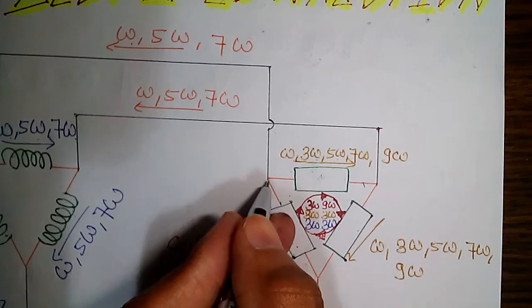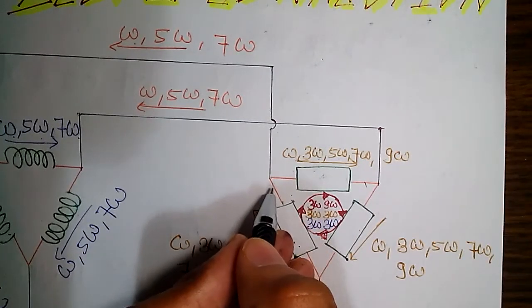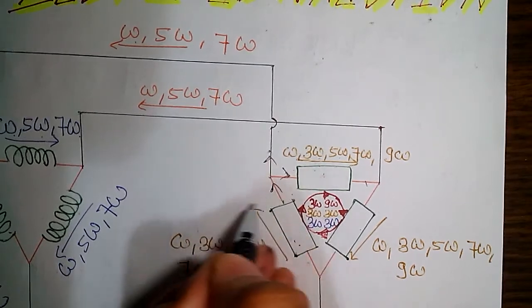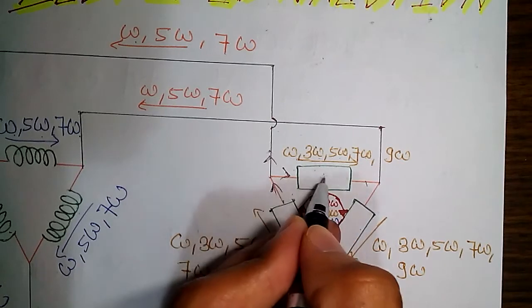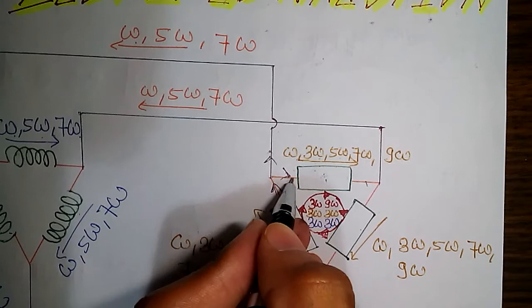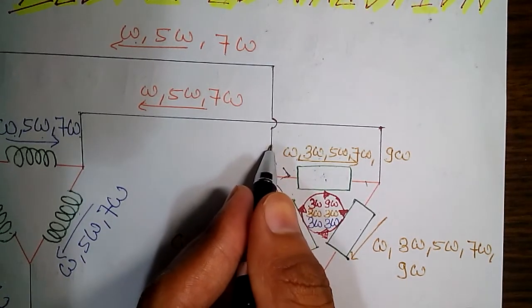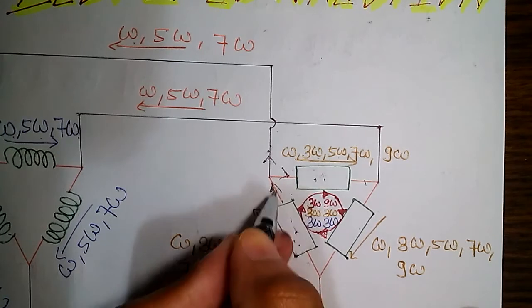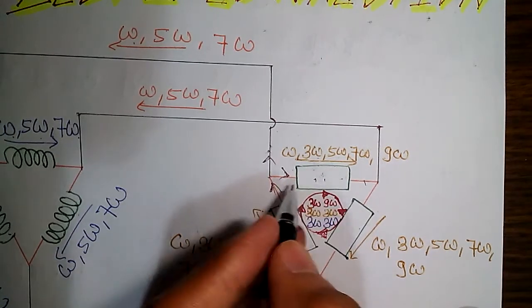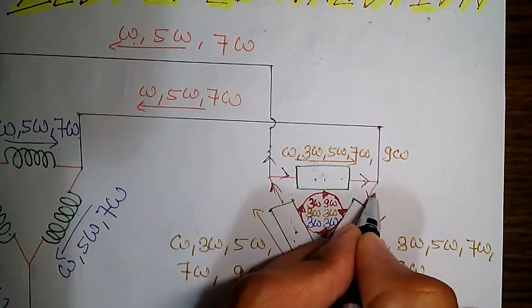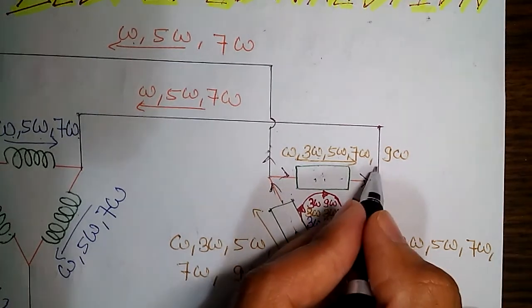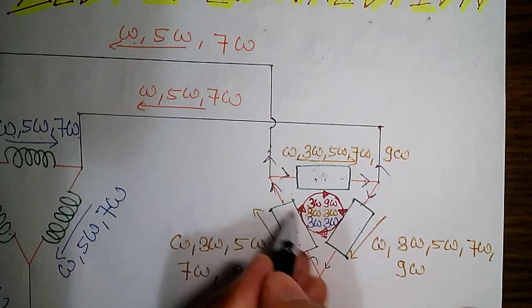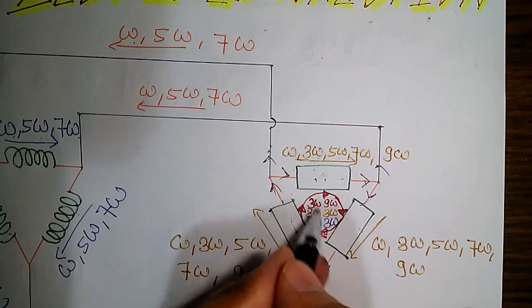Suppose my third harmonic current is going from here — this is my B-phase, B-phase third harmonic current going from here. From KCL, current going in and coming out must be equal. The third harmonic current of this line equals the third harmonic current of the other line, so all the current coming from one direction is going in that direction and no third harmonic current goes in the other line direction. All the third harmonic current coming from this direction is going in that direction because the third harmonic current value of this phase equals that of the other phase. Similarly this occurs here — so all third harmonic current coming from here goes here, and no third harmonic current will be going in the line. My third harmonic current will be flowing in this circle only and will not be going into the line.